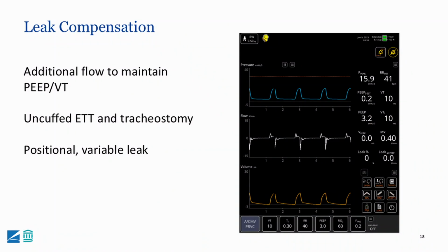Leak compensation is also something that's incredibly important. I mentioned before, one of the challenges in ventilating neonates, and again, especially extremely low birth weight neonates, is the leak around their artificial airway, whether that's an endotracheal tube or a tracheostomy tube. Most ventilators either provide additional flow or pressure to maintain the PEEP and tidal volume that's set or delivered. Your ventilator, though, has to be smart enough to know, as neonates are awake and moving, that these leaks can be positional and can be very variable. So to have a ventilator that will recognize a leak, compensate for it, and then recognize when that leak goes away and perhaps uncompensate for it, take some of that pressure or flow away, is very important.